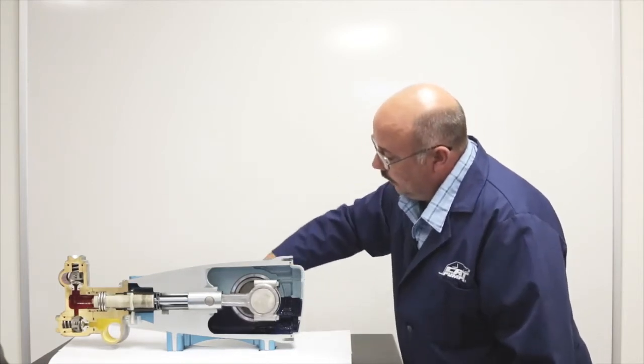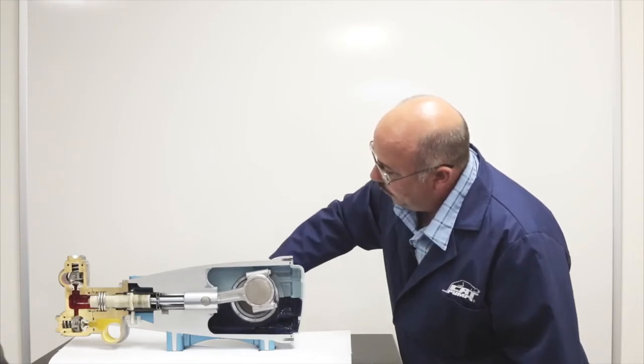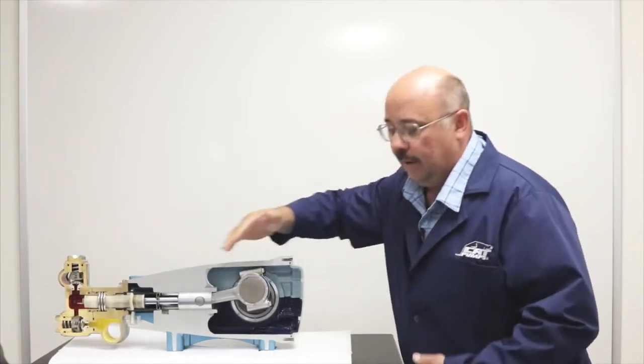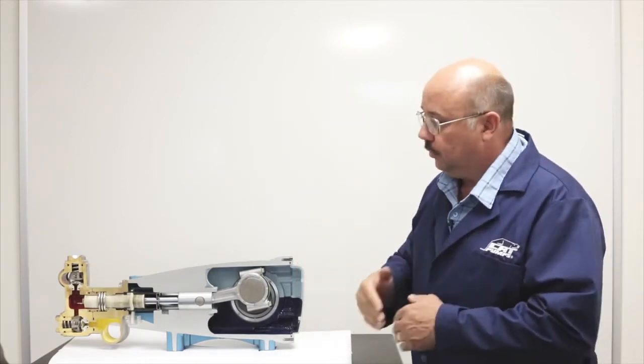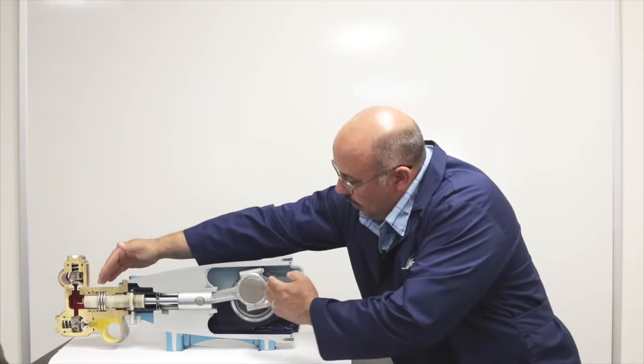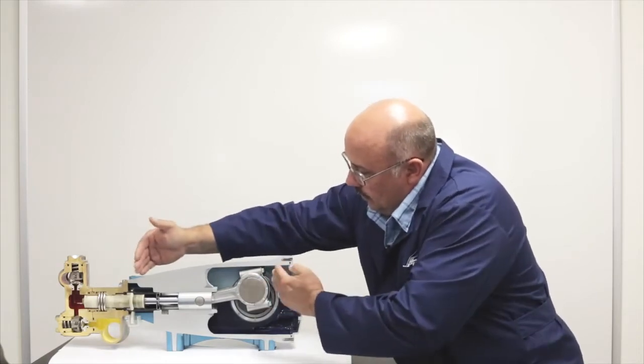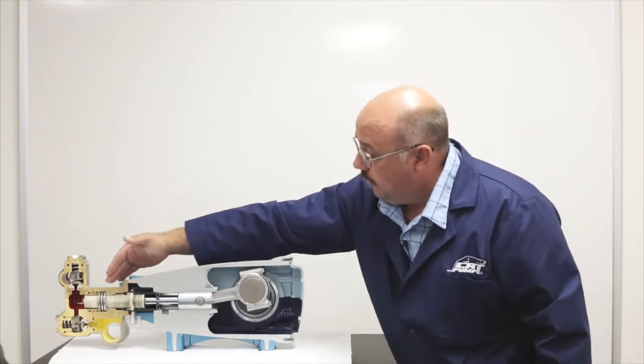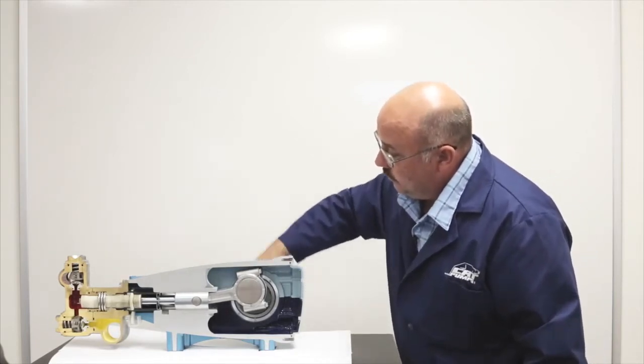But once we go over center and start to push that plunger back forward, now I'm compressing this chamber and I'm creating the discharge pressure and pushing that flow out. When that happens everything is in compression from here back to the crankshaft. There's a lot of compression because there can be two to three thousand pounds of force to push that plunger into that chamber.